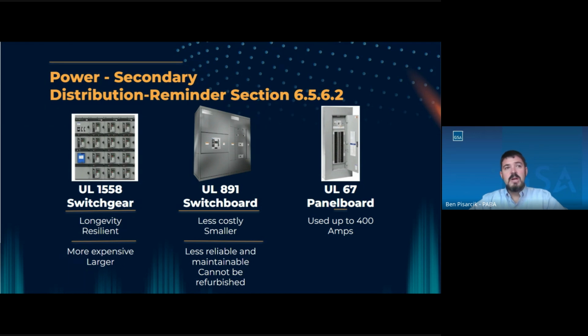So when you're laying out your electric room, you need to ensure that you have switchgear and the proper amount of cubicles laid out. And depending on how many breaker sections you're going to have, the size of your switchgear, it's going to drive the size of your rooms. So that's very important to have early on. Moving over to switchboards, UL 891. They are less expensive. They're typically smaller. They're less reliable. When I say reliable, you're not able to rack breakers out, rack new breakers in, get things back online, that type of situation. You basically have to kill the entire board to do maintenance and those sorts of things. So the availability of that particular facility would be less typically in a switchboard situation, I think is a good way to say that. They cannot be refurbished, they're typically replaced. So that can be an issue if you need to replace the entire gear as opposed to refurbish it.